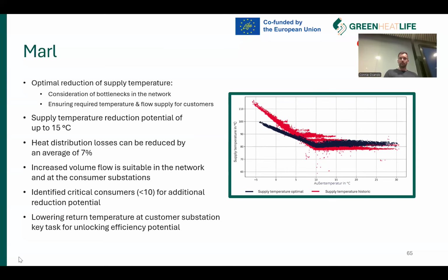So you have, from a historical point of view, very high supply temperatures, and now we know to what extent we are too high. But this is systematic for many of the grids in Germany. You can do this kind of optimization for many grids; it's similar. So we are planning it. Of course, each district heating system is individual, depending on pipes installed, customers, substations, direct or indirect. So it is very unique. However, we have potential in nearly each network, maybe not as high as here in Marl. Still, a few degrees Celsius we can decrease in nearly each network.